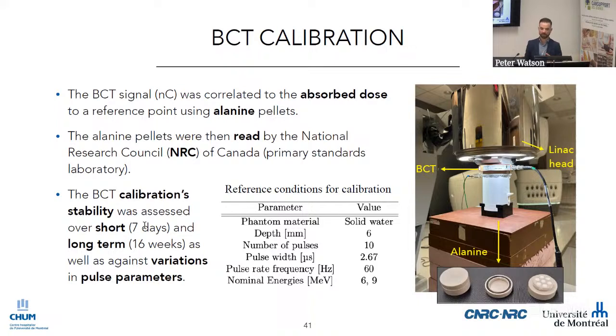So we created a dose to charge relationship, the charge measured by the BCT versus the dose absorbed at a point downstream of the BCT, the same way we do for monitor chambers in a standard linac. And we wanted to see how stable that relationship was, and whether we could rely on it to report the dose delivered in FLASH conditions. So we've done this calibration.